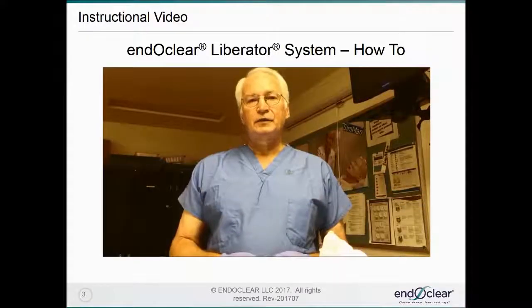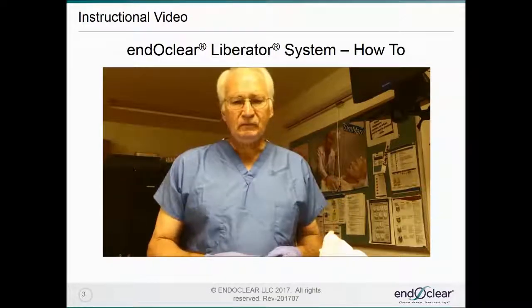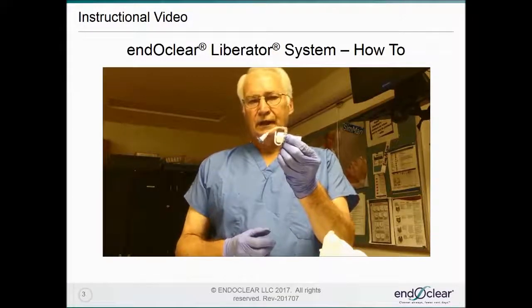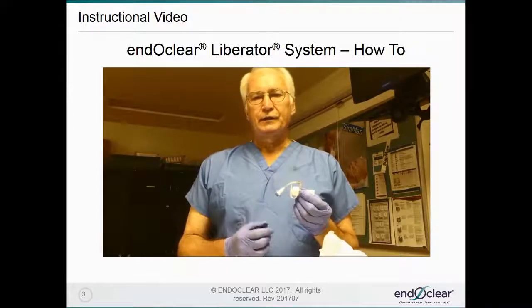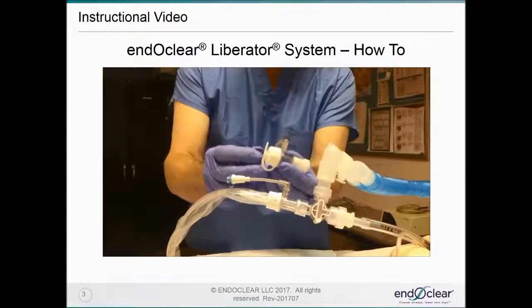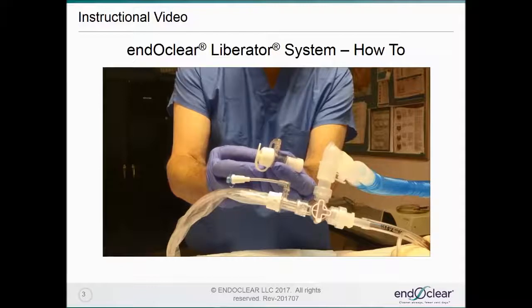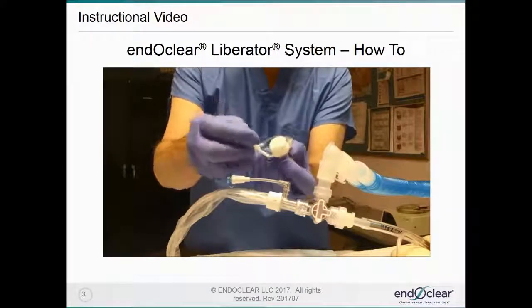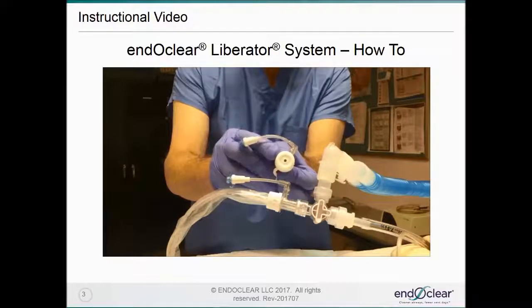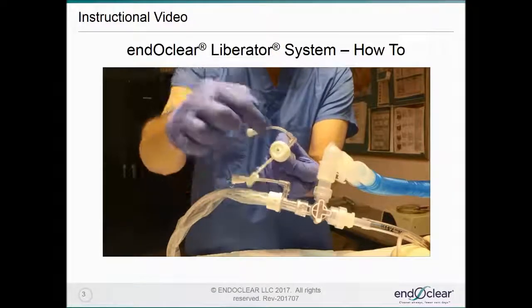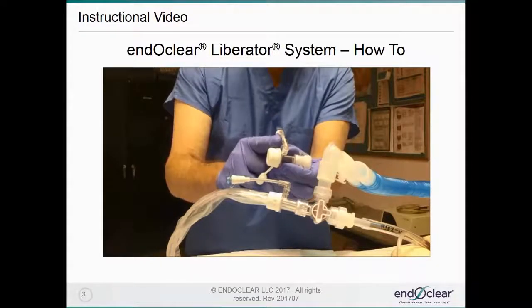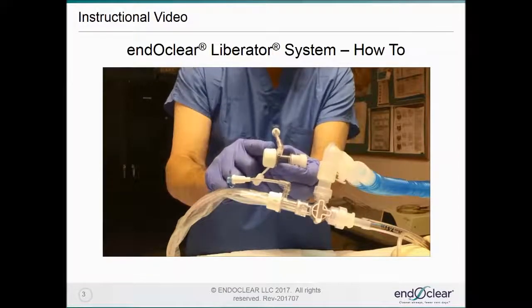Intubated patients sometimes require instrumentation of their airways, either for bronchoalveolar lavage or bronchoscopy while in the ICU. This is the ENDOCLEAR bronchoscopy adapter that works with the ENDOCLEAR Liberator airway maintenance system. The bronchoscopy adapter is also a modular component of the system. It has a flexible diaphragm that accommodates size instruments between 3 and 8 millimeters, and once the instrument is inserted, it is air tight to 40 centimeters of water pressure.